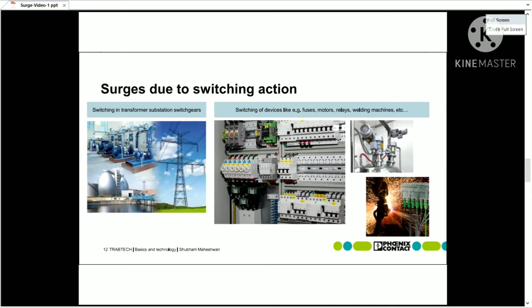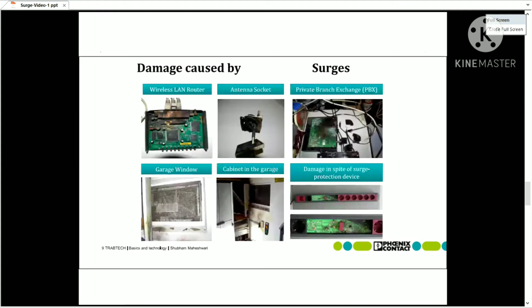Another type of surge which is very common and equally damaging is the switching surge. These surges are generated due to the extremely high current changes such as short circuits, switching on and off of large electrical equipment such as contactors, motors, chillers, compressors, heavy-duty welding machines, etc. Check the equipment damage by switching surges. One of the most common causes of a switching surge is when high voltage, low voltage, as well as signal cables are laid in the same cable tray without sufficient separation between them.